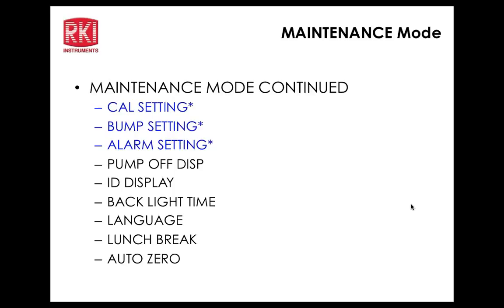Okay, next on this menu is IR auto range. So just get into that real quick. So auto range is a capability for. One thing on the PID, I remember that Riken. There's no reason to have any 0 suppression on a PID. You have that sensor so you can read low levels, and it does say you can set it to 2% or whatever, but it's always 0, even if you try to set it to something. Yeah. All right. So here, the next one, IR auto range. You can select either auto range or low range, actually.